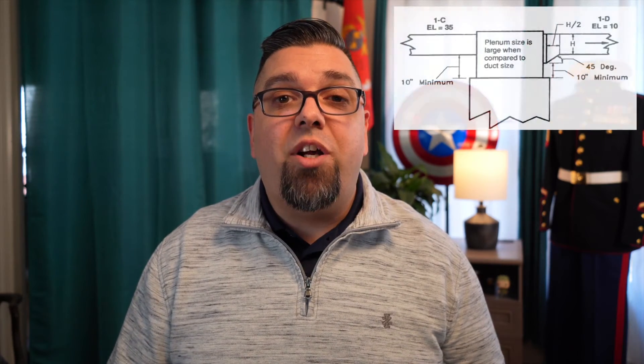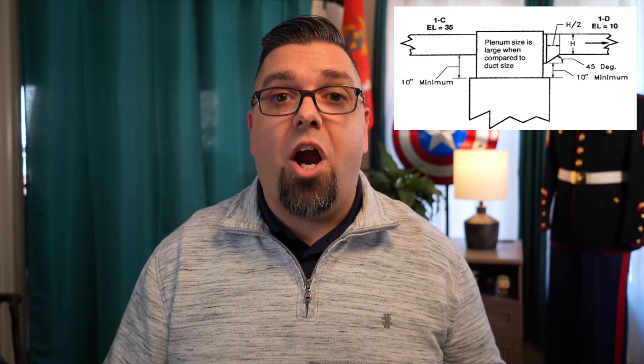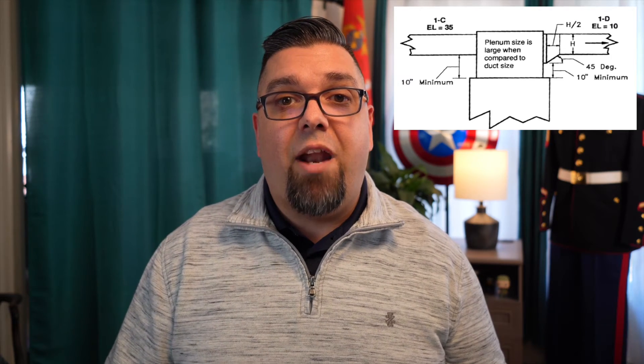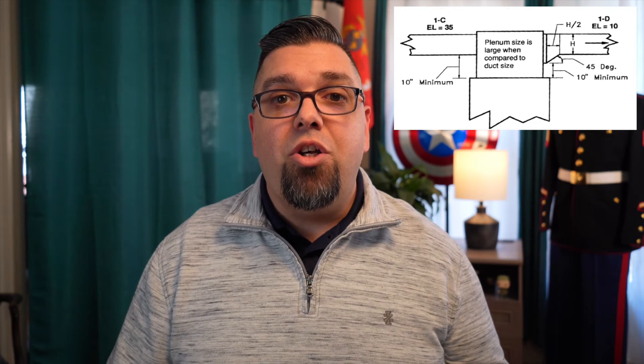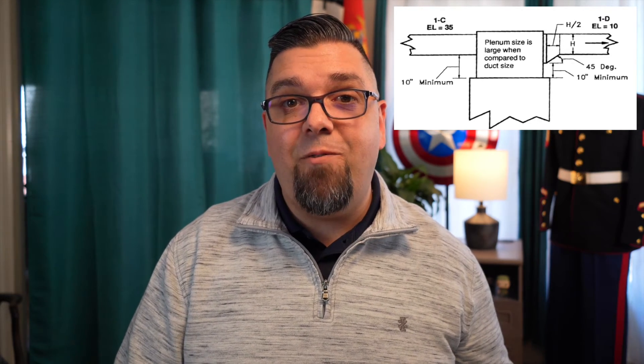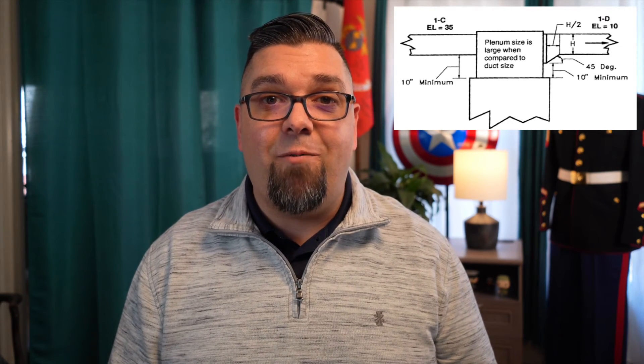The number one place to look for high fitting values is as close to the air handler as you can — the typical plenum starting collar. If that's a bull head tee, you're going to have serious restriction and a high equivalent length value. But if you come off that plenum starting collar going into the trunk at a 45-degree angle so it's easy for the air to make the turn, you could knock a 120-foot bull head tee fitting all the way down to 10 feet very easily. And maybe now your duct work is sized right for that smaller system.